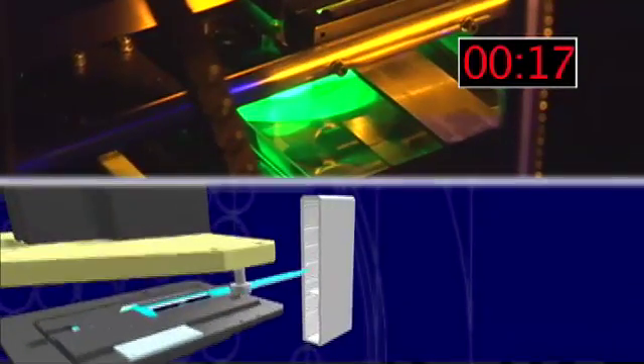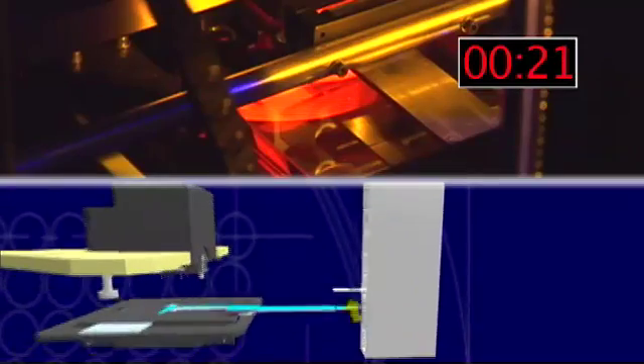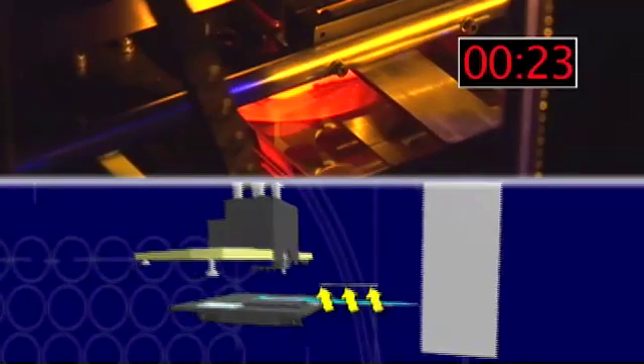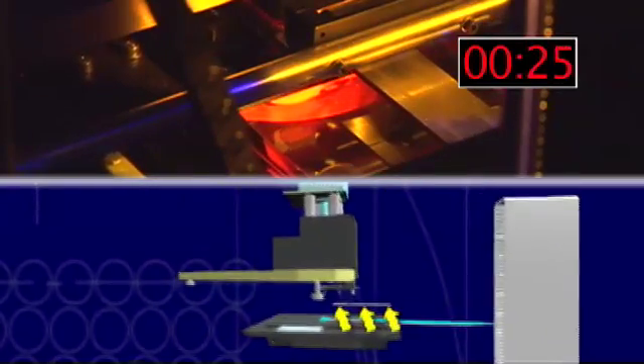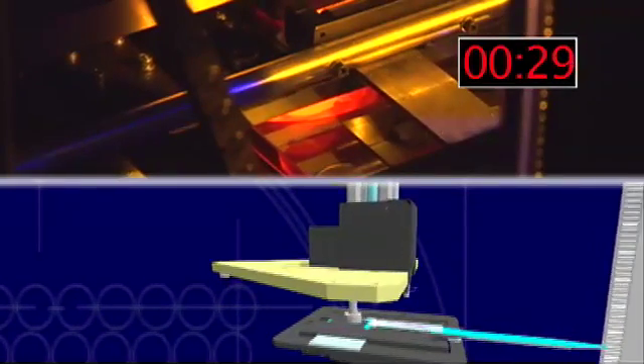Slides are organized in racks that store 40 slides each. The slipstream system hovers each slide and gently transports it to the slide scanner on a cushion of air. During scanning, the slide is held by a vacuum, not mechanical claws.